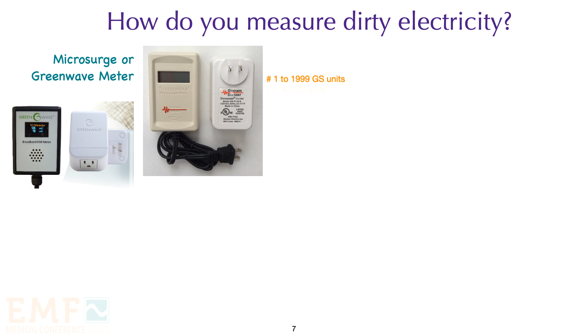You can measure dirty electricity with either a microsurge meter or a green wave meter. Ideally, values should be less than 40 GS units. You can also measure and record dirty electricity with a scope meter, and this is what dirty electricity looks like. The peak-to-peak value is 650 millivolts in this example, and values of 10 millivolts adversely affect dairy cows and humans. The relationship between GS units and frequency and voltage are shown in this graph and will be discussed in more detail later.